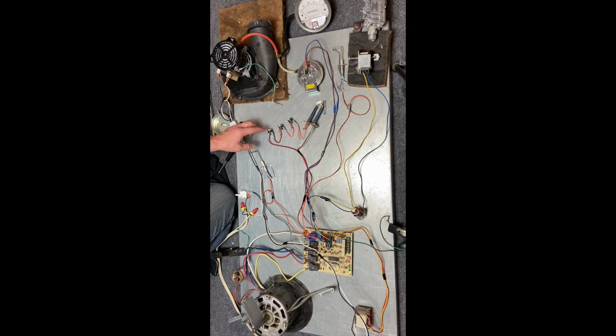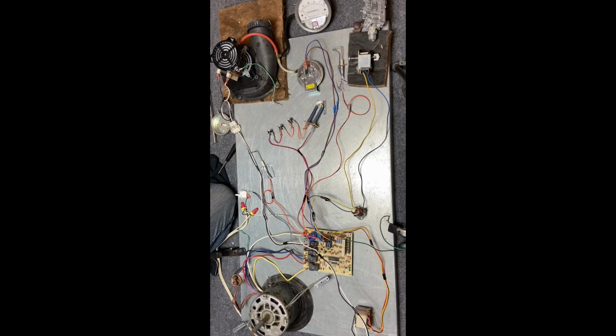Now this limits the rollout. If the flame was to roll out, it's going to be a big issue. So we're going to manually push this in. You see the control board did 2 things. It immediately energized our combustion fan motor, or inducer draft motor, to force the draft to that heat exchanger to protect it. It also is energizing our blower motor to move air across the heat exchanger so it cools off. Because it doesn't know if it's one of these or one of those, so as a safety factor, that's what it does.